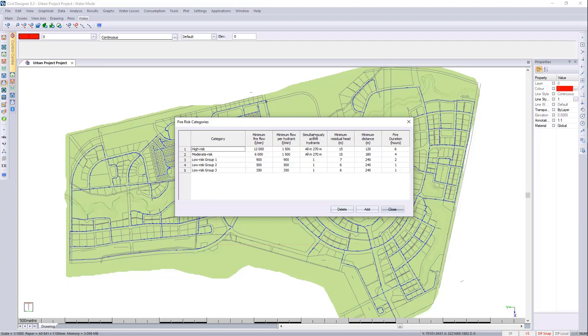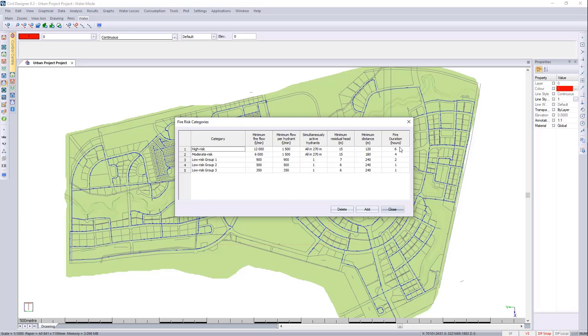Looking at the different fire risk categories, we have minimum fire flows. We also have minimum fire flow per hydrant. We will then also have how many hydrants will be active during the analysis. We'll have the minimum residual head, as well as the minimum distance spacing apart. And then we'll also have your fire durations for each one.